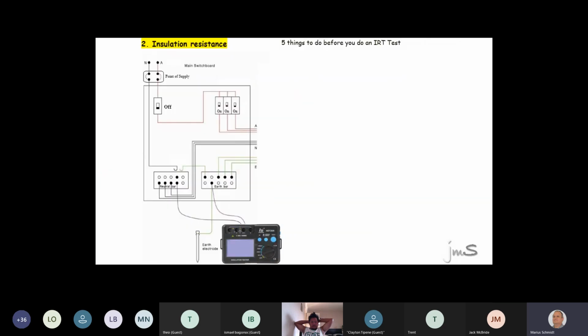So guys, when I look at my insulation resistance tester, there are five things you must always remember before you do an insulation test. Firstly, make sure that your supply is off. Have a look there at the top left, the supply is off. Got it? Secondly, make sure that your MEN link is removed. Why? Where do you test between when you do an insulation test? Earth and phase, earth and neutral only. You never ever test between phase and neutral, except if it's just a loose piece of cable. If it's a loose cable and nothing is connected, you can do an insulation test. But if one side is connected to the house, you can never test it because you're going to damage stuff. So you test between earth and phase, earth and neutral.